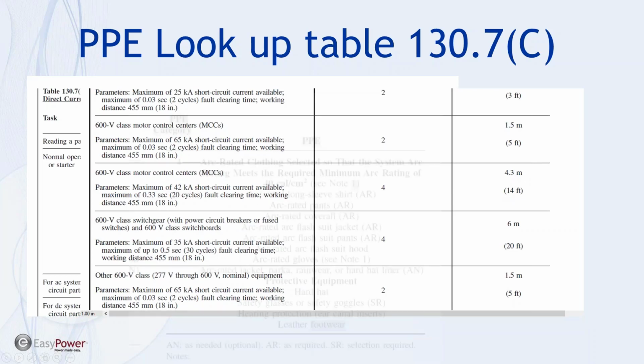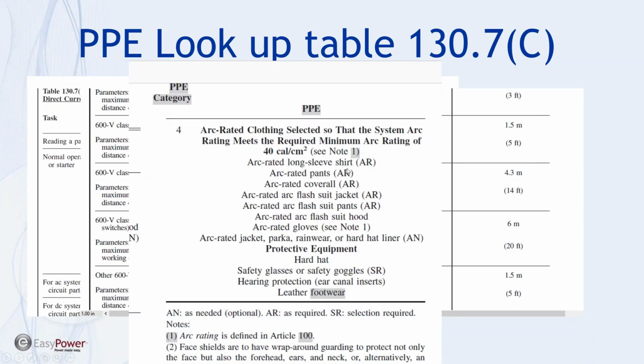So far, so good. If we go to the final page of this lookup table, we see category 4, and again, it's PPE category. Don't even get this confused with HRC category. So PPE category 4 means that we have to have PPE rated to 40 calories, and it needs to cover these elements in our dress down or our layers. Now, bear in mind that we can only use this table if we can verify the equipment's been properly installed, that it's been properly maintained, and it's not showing any evidence of pending malfunction.